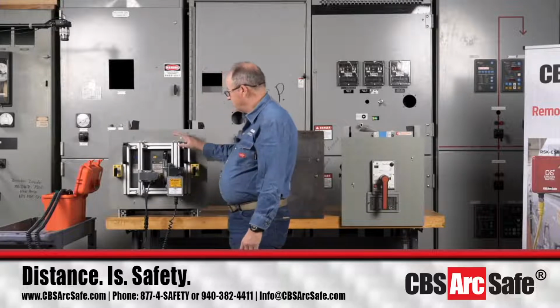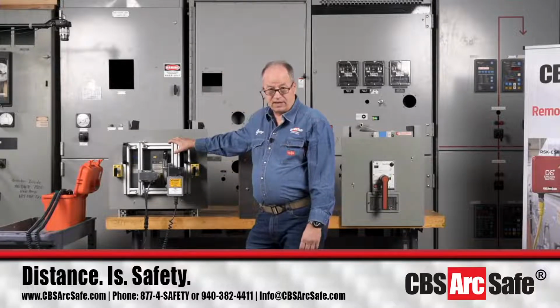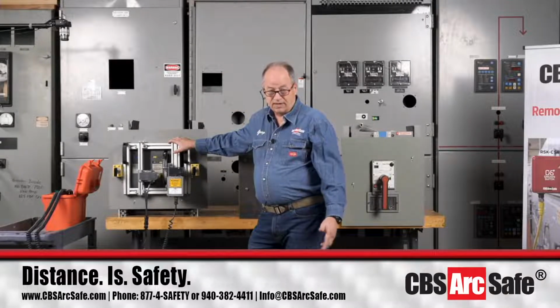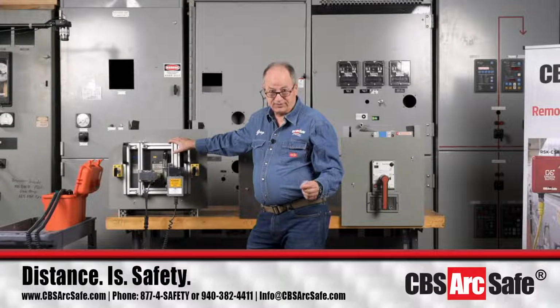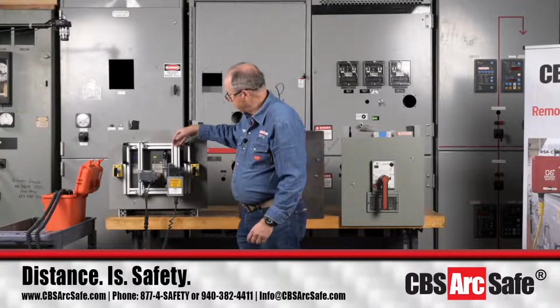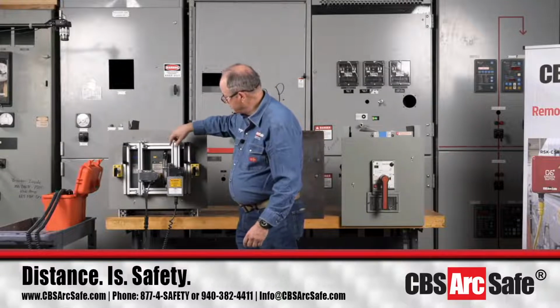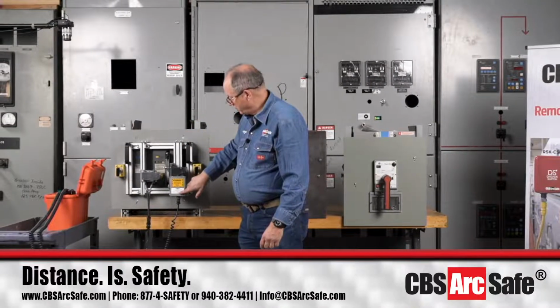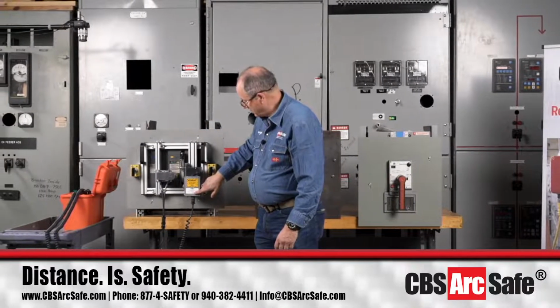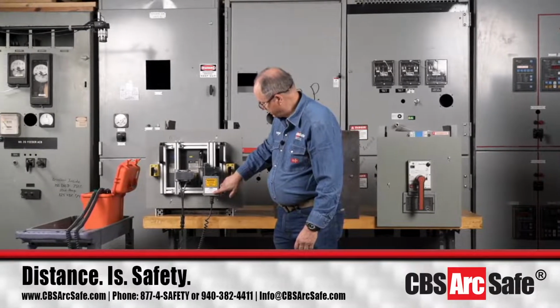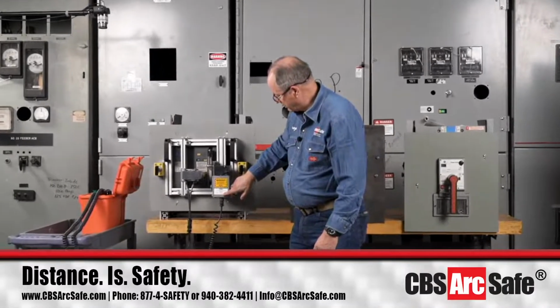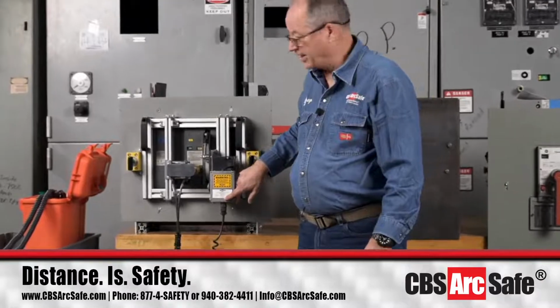This is made to accommodate all of the 800 to 3,000 to 4,000 amp frame size series. I'll caveat that - we'll talk about some differences based on mounting in a bit. But basically it goes on, around the face of the breaker. Then we set up the RSO 3D, which is going to operate this with 6 strokes, and we set our times at 6.8 and 6.5.